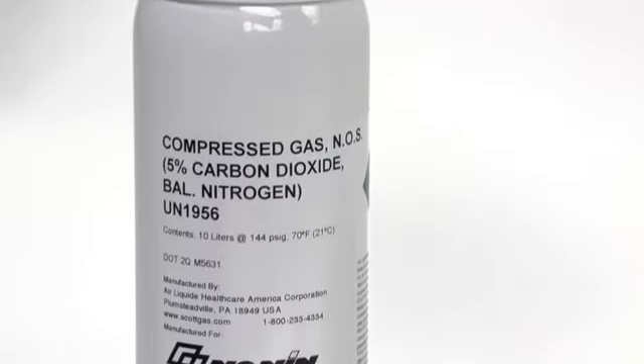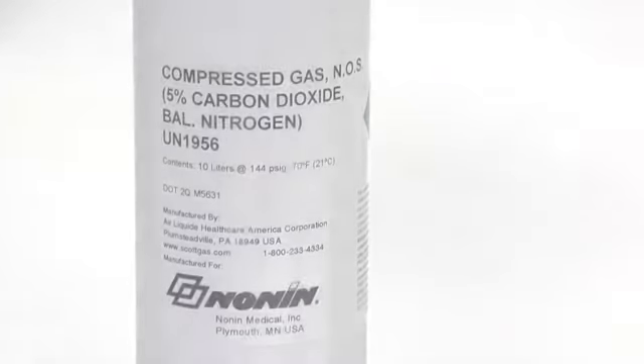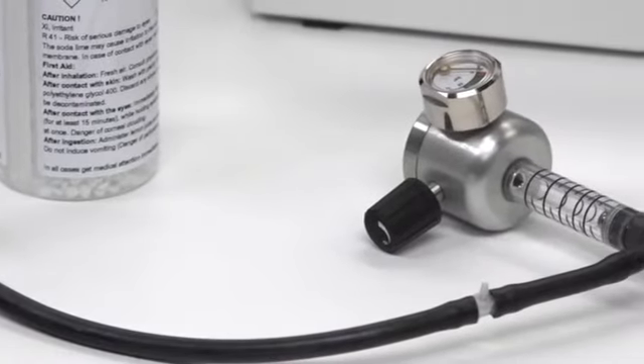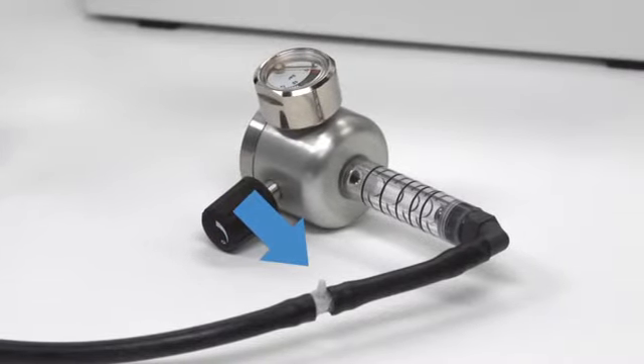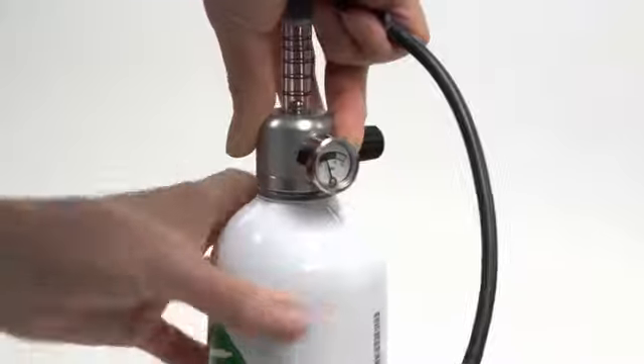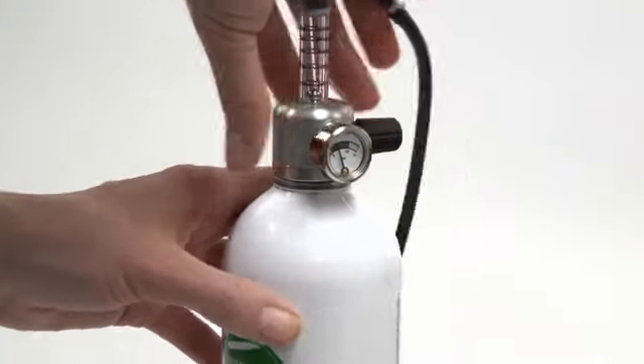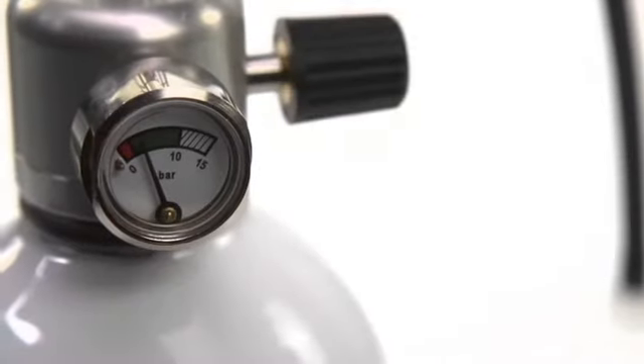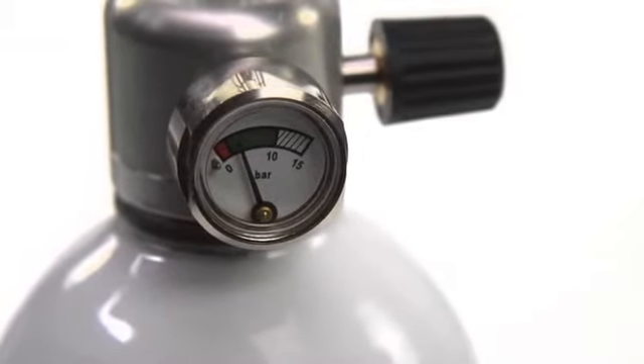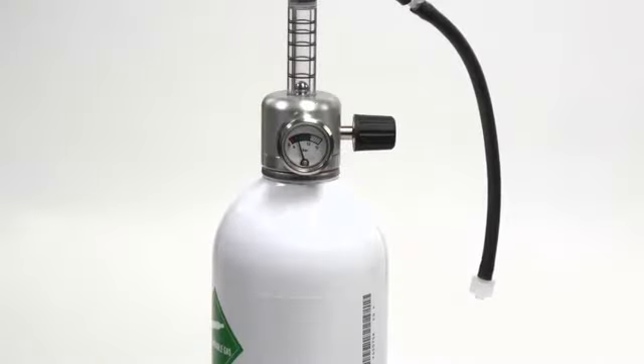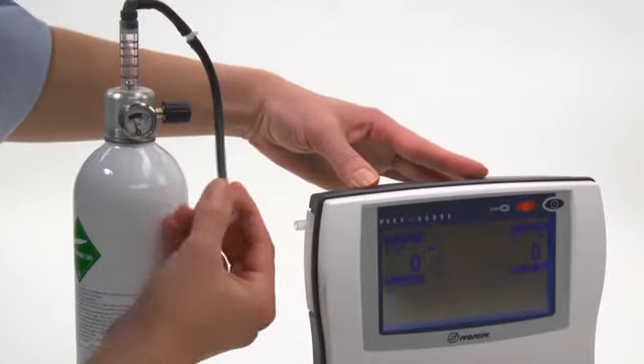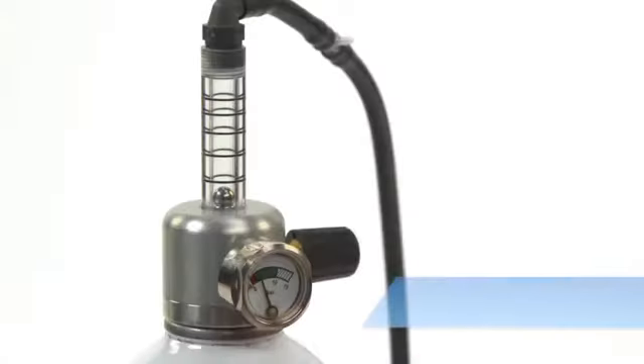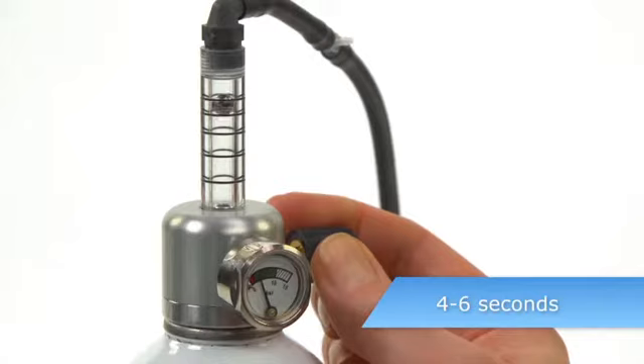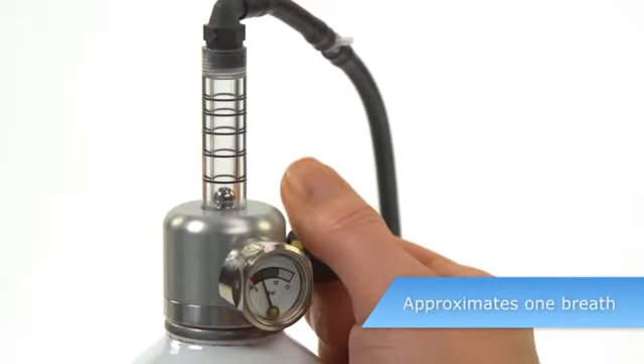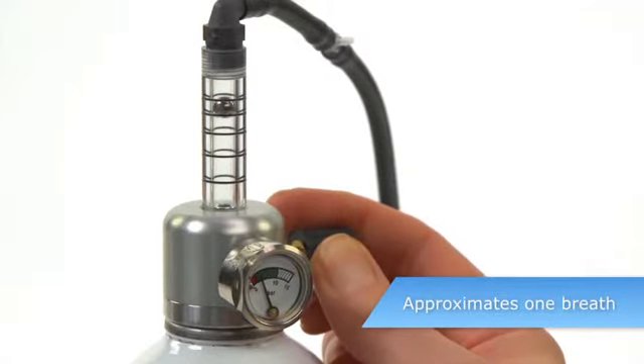To perform the verification procedure, attach the 5% CO2 verification gas bottle with the valve to a sample line with a T-connector on the valve. Verify that the gas valve needle is in the green zone of the dial indicator. If the gas valve needle is in the red zone, the CO2 bottle is empty and should be replaced. One CO2 bottle can be used for approximately 100 verifications. Connect the sample line to the trap. With the monitor running, open the valve on the gas bottle for 4 to 6 seconds to deliver about 200 milliliters of gas. This approximates 1 exhaled breath.